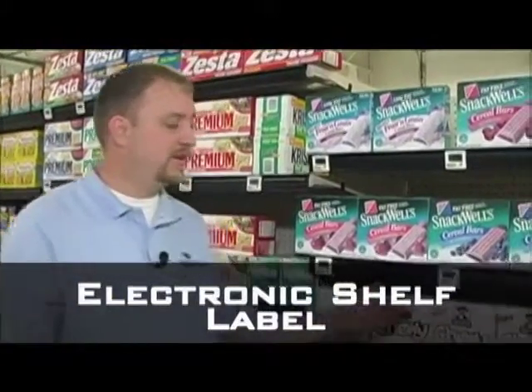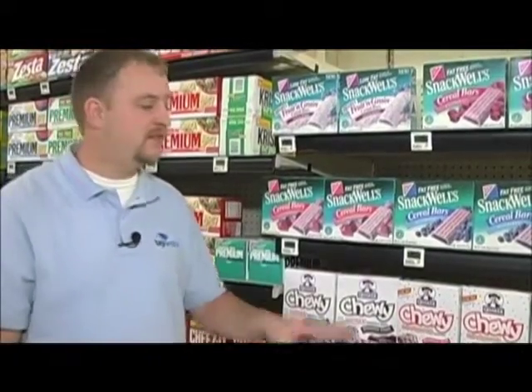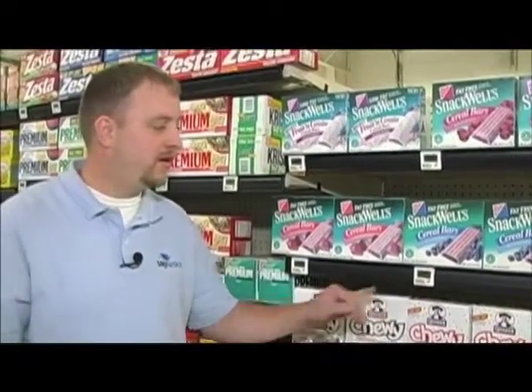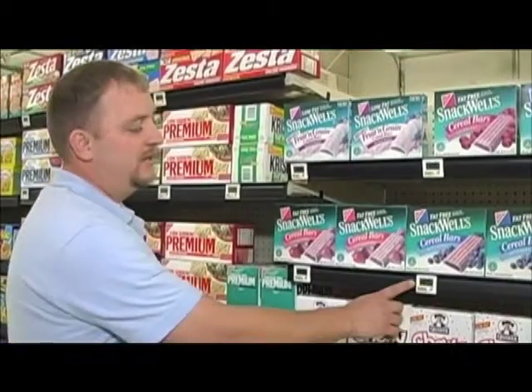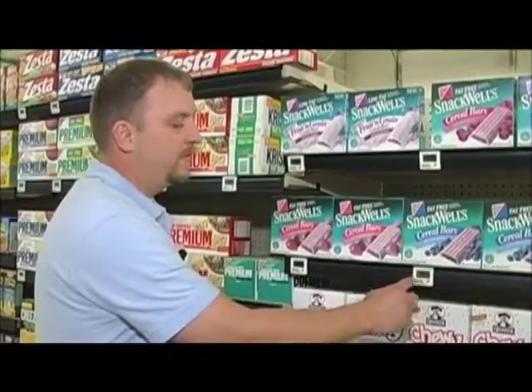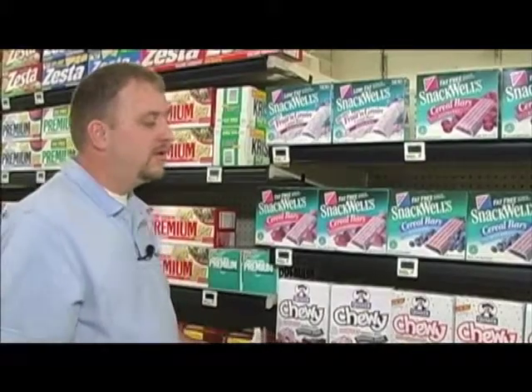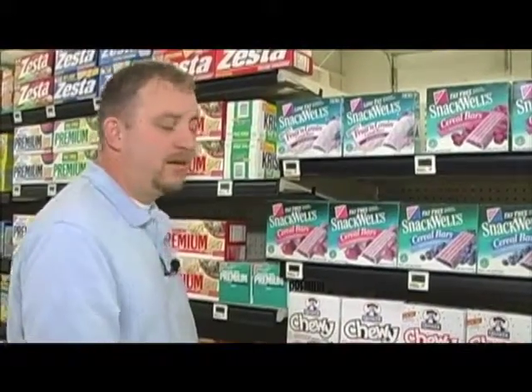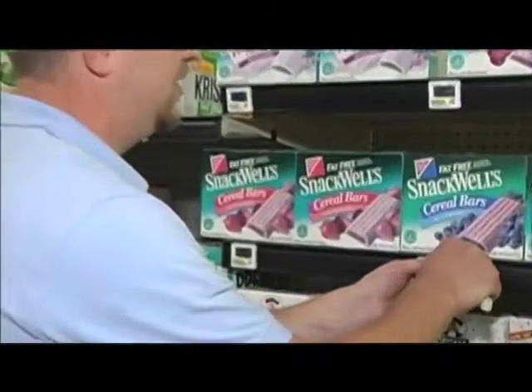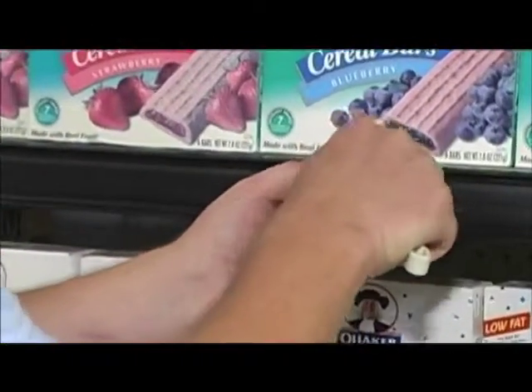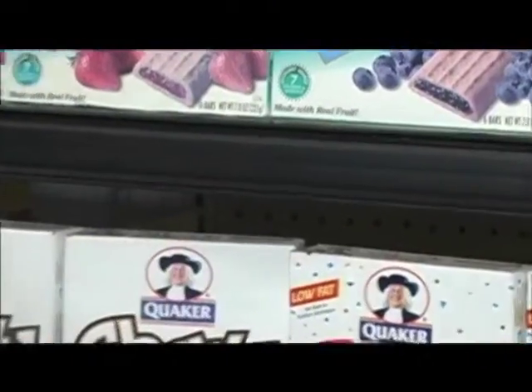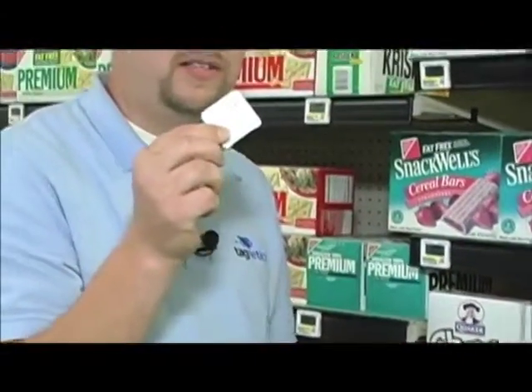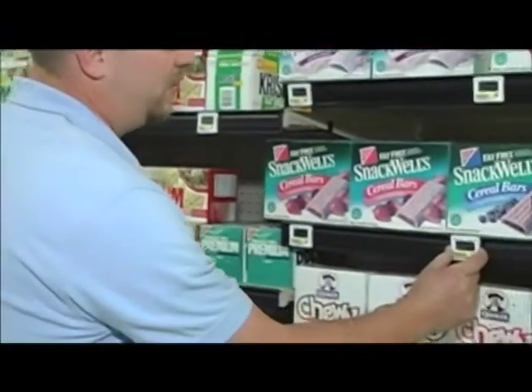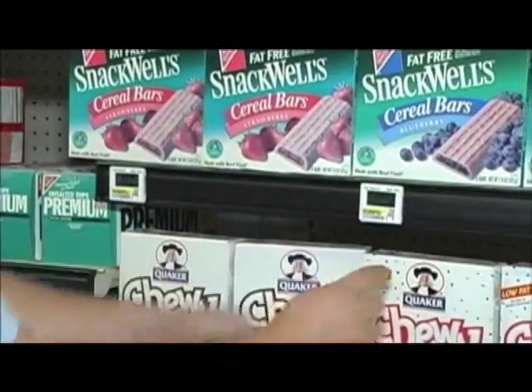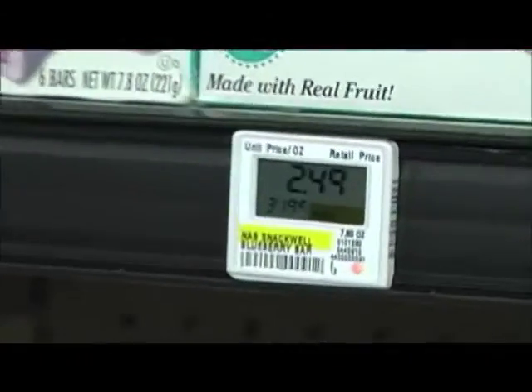Our final component is, of course, the electronic shelf label. The electronic shelf label is a unique device in that it has no battery. It is inductively powered through the rail. Inside the electronic shelf label is a coil. The coil is what enables the electronic tag to get its power and communications. As you can see, the tag can be removed from the rail, and there are no attached wires. It is all inductive. Once placed back in the rail, you can see it boot up and get its price.